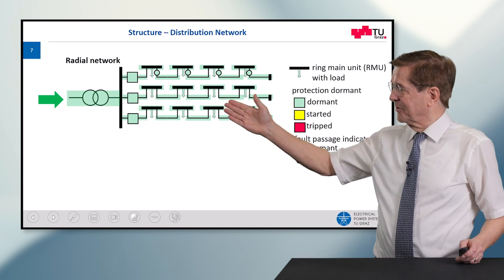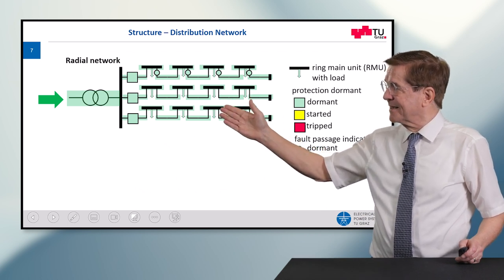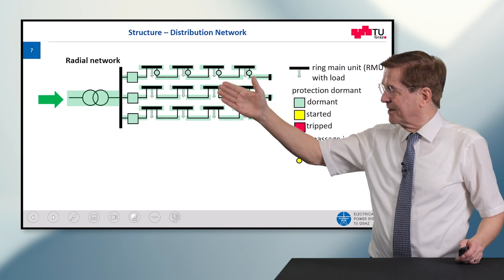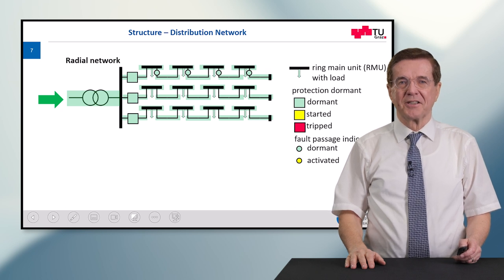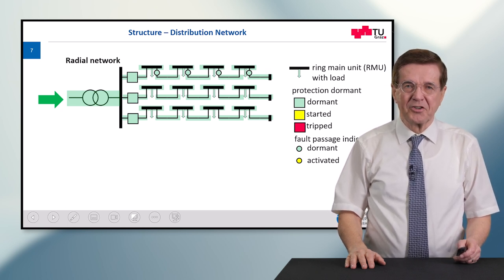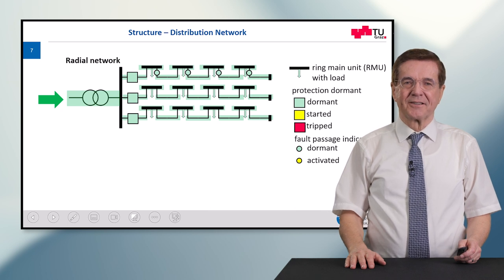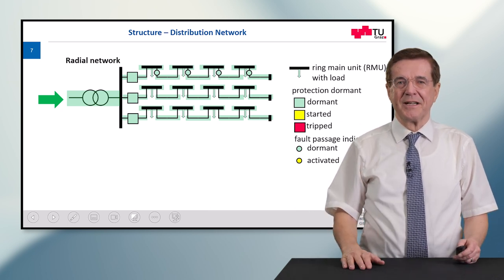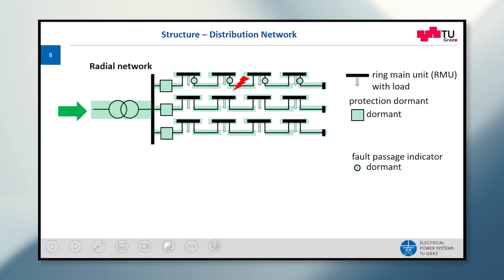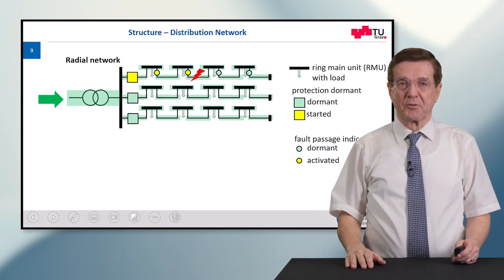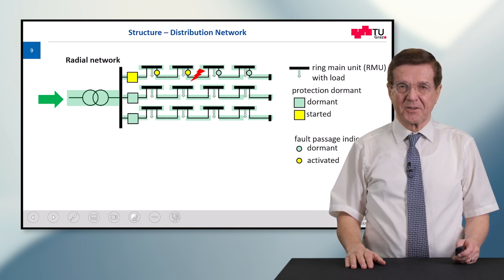Here you can see to my right side a typical radial network. The power and energy come from the left side through the transformer and are then distributed to each individual consumer, connected to the horizontal stripes — these are the so-called ring main units or local substations. Now a fault happens: a short circuit causes a large current from the transformer through the feeder to the fault point, and consequently the protection is triggered and the fault passage indicators pick up.